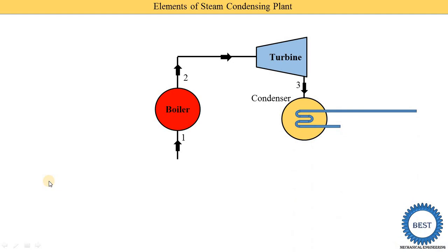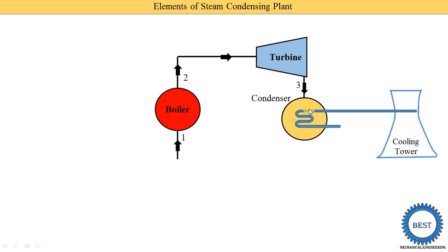In this diagram, you see this is the surface type condenser. The steam is passed from outside these tubes and the cooling water is passed through these tubes. The cooling water absorbs the heat energy from the steam, so the temperature of the cooling water is increased and we need to cool this hot water again.